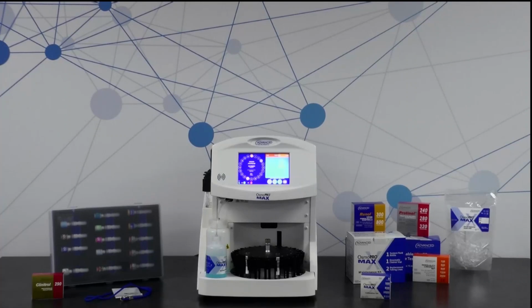Okay, how long does it take to run one sample for routine and stat? So regardless of the sample type, it's about 5 minutes a test on board the instrument. Again, it's a little bit longer than the Osmo One or the Osmo Pro, for example, but the advantage of the Osmo Pro Max is that you don't have to stand in front of the instrument and manually do anything to run the test. So even though it takes about a minute or so longer, you can load as many samples as you want onto the turntable and just walk away. So you don't have to stand around babysitting the test and basically take up all the time you could be doing other things, just running osmolality testing. So that's really the value that the automation of the Osmo Pro Max provides. But yeah, 5-minute test turnaround.